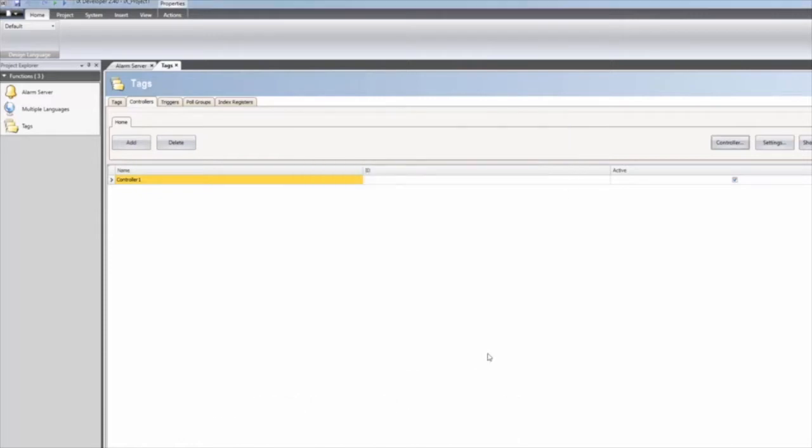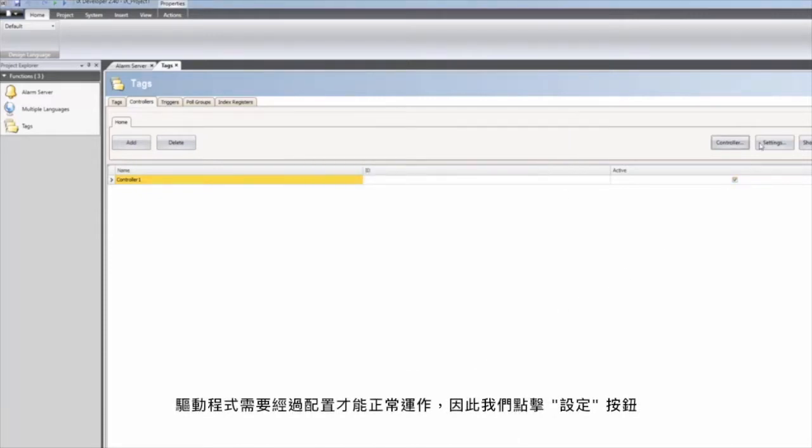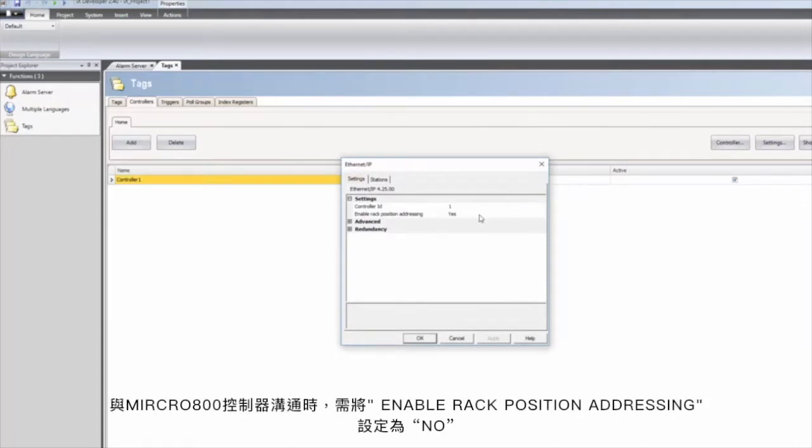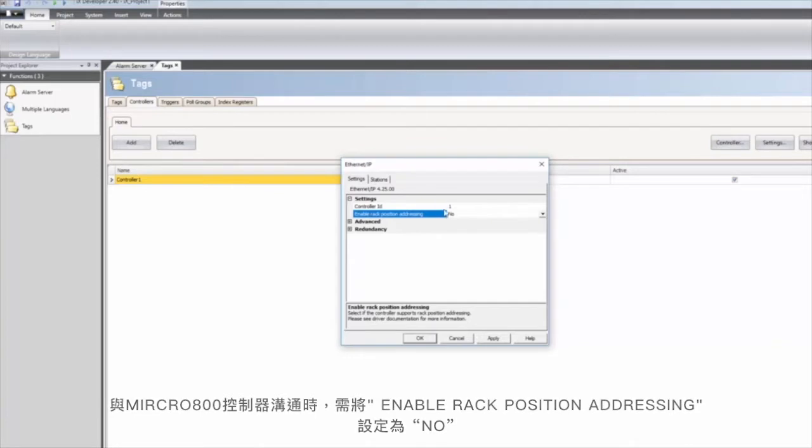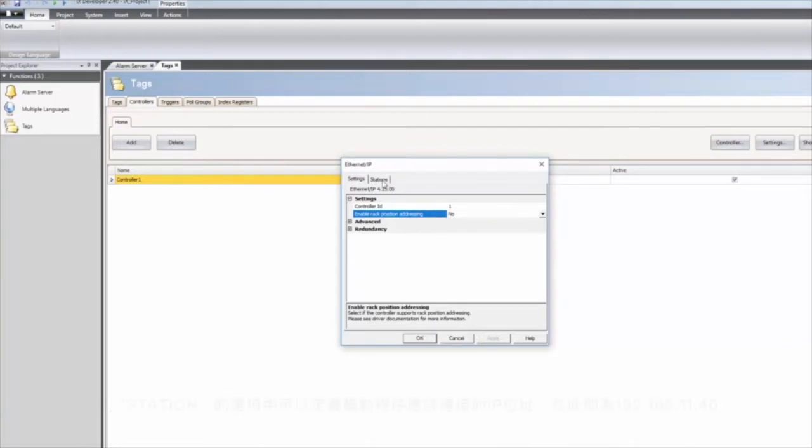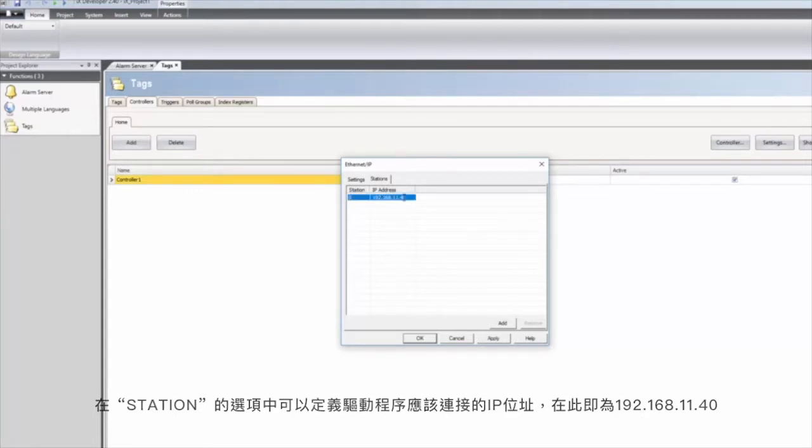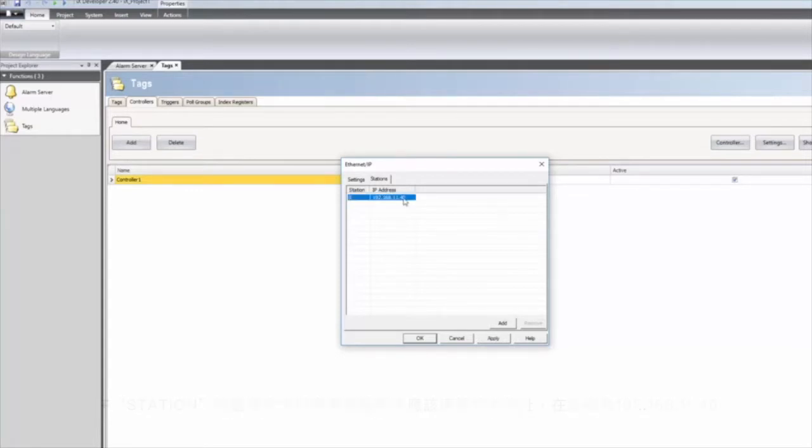The driver needs to be configured in order to work properly, therefore we click on the settings button. When communicating with Micro 800 controllers, the enable rack position addressing should be set to no. In the stations tab it is possible to define the IP address that the driver should connect to, in this case 192.168.11.40.